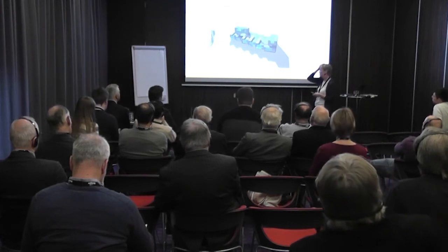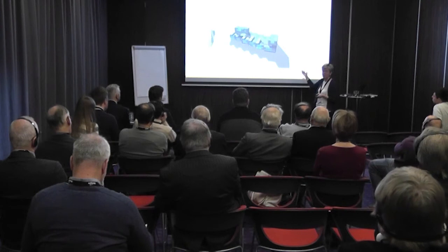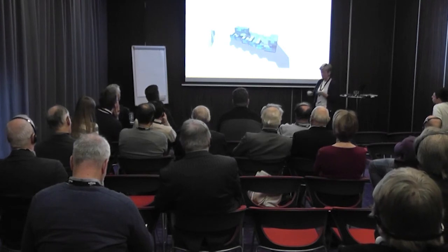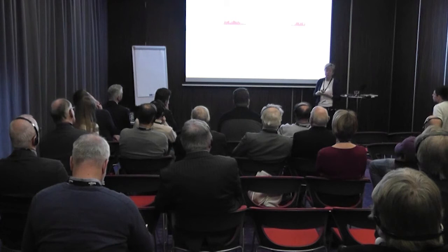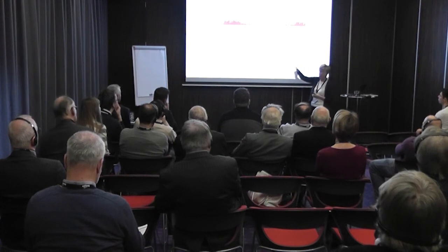And we had a building model. We were simulating this building in IDA ICE, and we combined the results from IDA ICE with the measured data on all this that is cooled directly into a huge spreadsheet. And so we got this load profile. This is every hour during the year. Here you can see the heat pump in red, and the yellow is district heating that you see in winter, where we need some extra. And this here is process cooling, the blue-brown band. This shows why we decided we don't need anything other than this, because it's such a huge amount. And this darker blue is ventilation and not for cooling. So this is for the ventilation when it's hot outside.